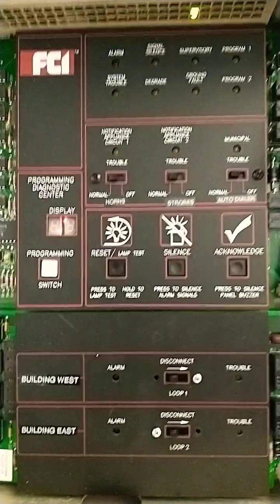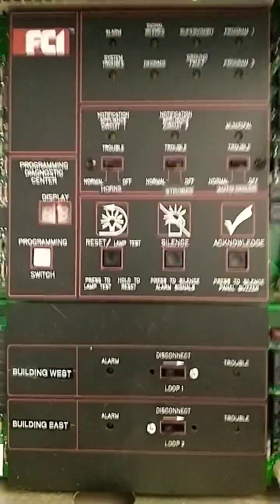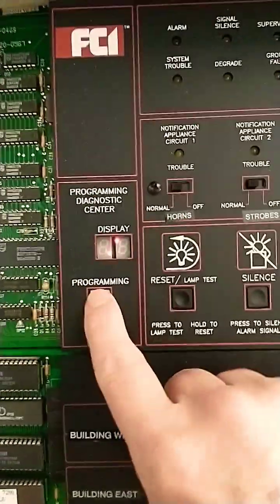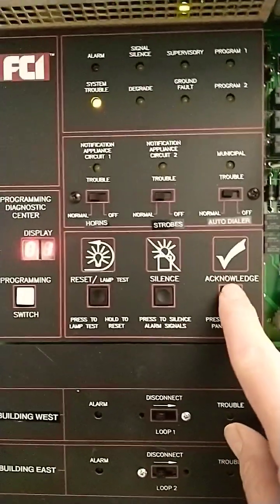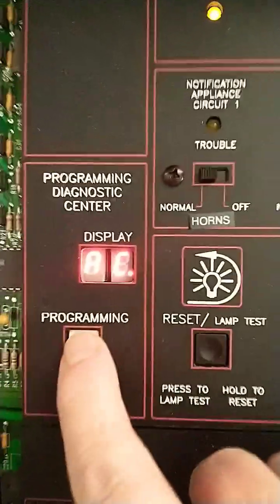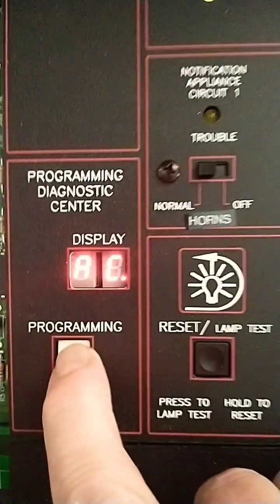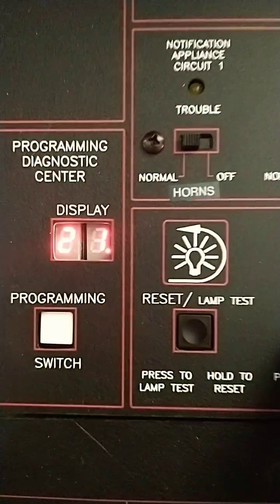How to place an FCI SC7200 system into Audible Walk Test. Start by pressing the programming switch when 01 is displayed. Acknowledge X as the Enter key. Then you'll see AC for access, at password level 2. This will do the tens digits and the silence will do the units digits.